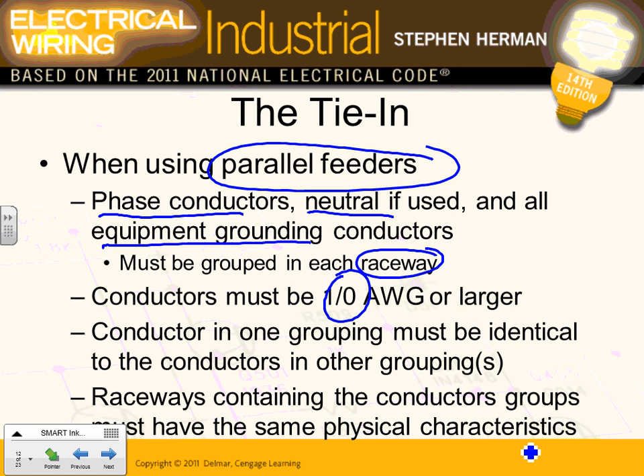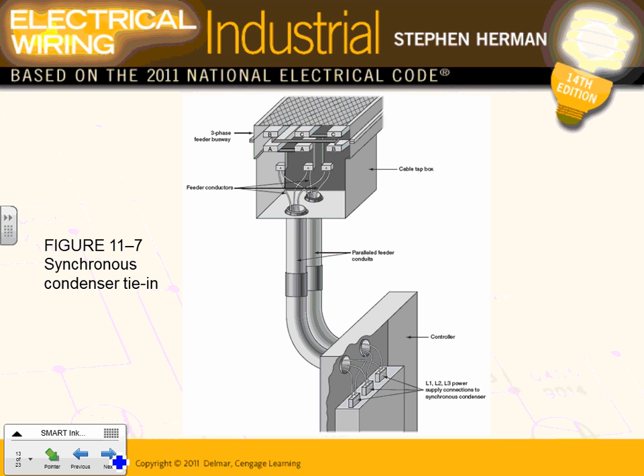Any comments, any questions guys about paralleling conductors? This is just set on the side about paralleling conductors because they are paralleling for the condensers. Okay, here are your conductors paralleled right here. When you parallel them, all the conductors of the same circuit have to be the same, including the neutral and the grounding conductor.